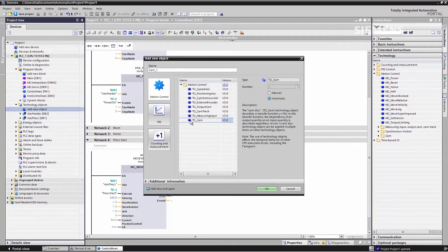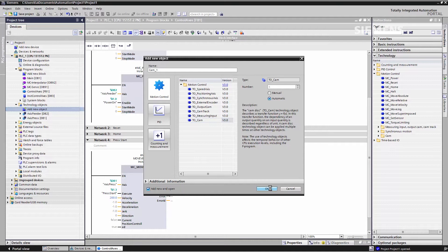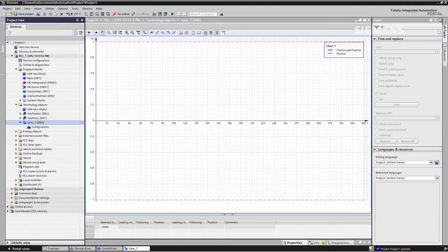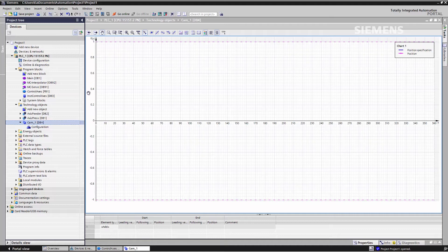To do this, we create a technology object CAM. In the CAM disk editor now appearing, we can very easily define and optimize the CAM disk in various ways. The x-axis represents the position of the master axis — in our case, the press. The y-axis of the diagram indicates the slave axis — in our case, the infeed.